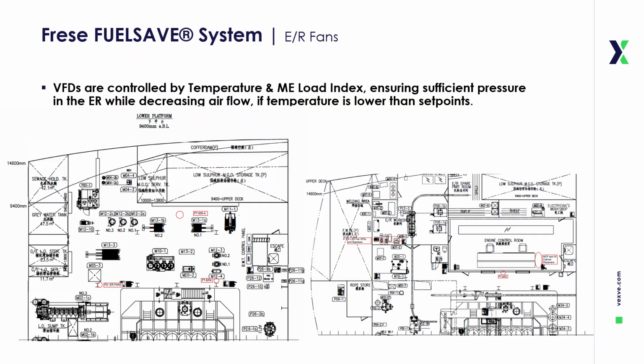Conversely, if the measured temperature falls below the predefined set points, the system reduces fan speed, decreasing airflow while still maintaining the minimum static pressure required in the engine room. The control loop ensures that ventilation demand is precisely matched to actual thermal load, avoiding the inefficiency of running fans at full capacity under all conditions.